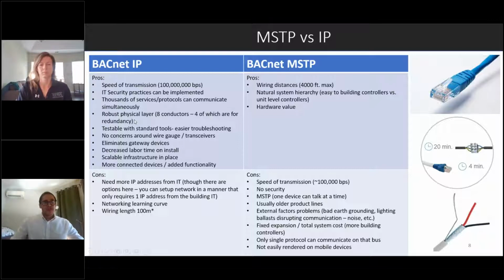So it's a very robust physical layer. Four of the conductors are purely for redundancy, so it's easy to maintain and definitely easier to troubleshoot. At Distech Controls, we noticed a lot more phone calls for troubleshooting issues, mainly around grounding, with MSTP controllers - all that goes away once you transition over to IP. You have a lot fewer issues in terms of just getting that communication working.